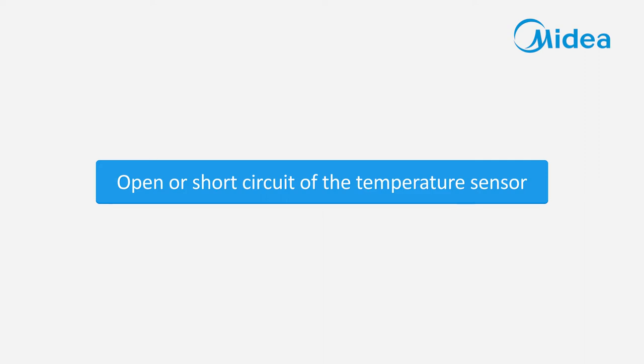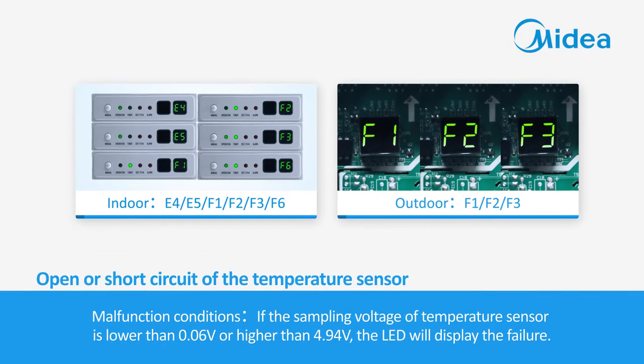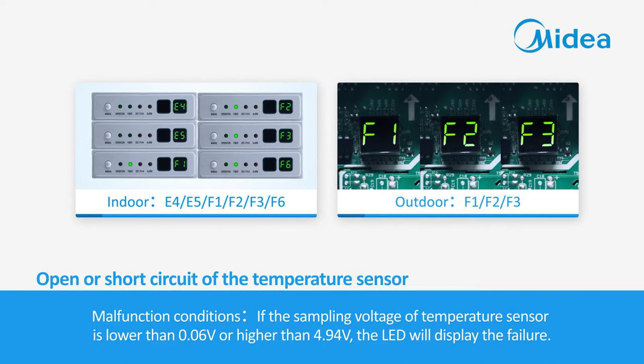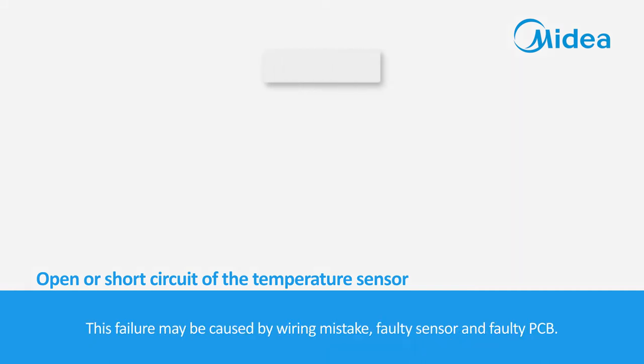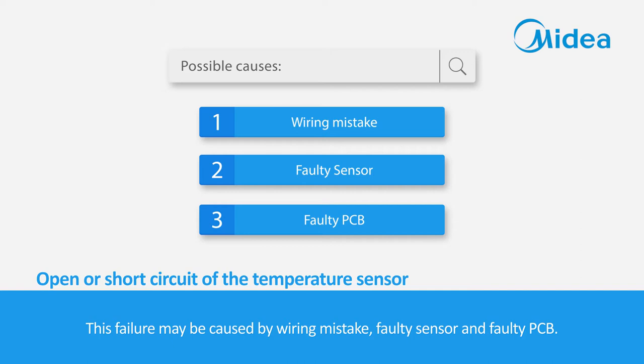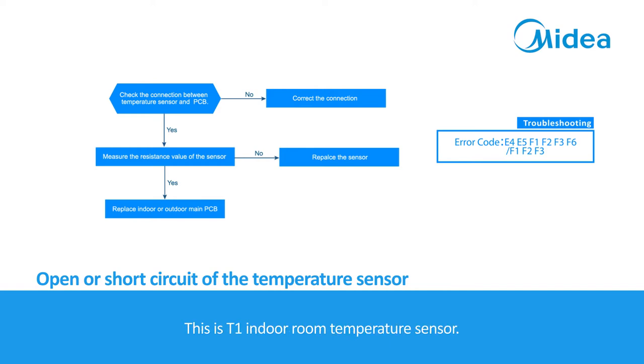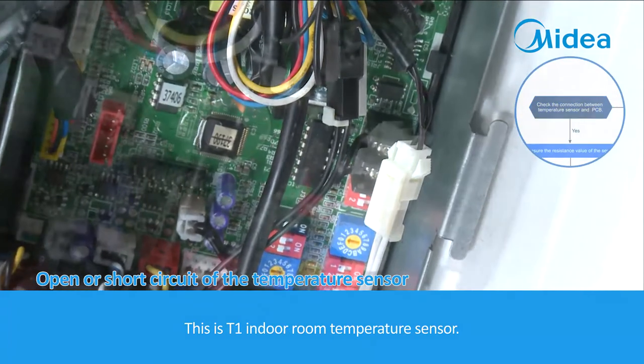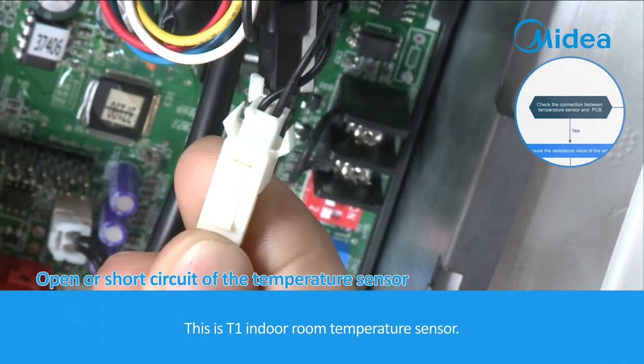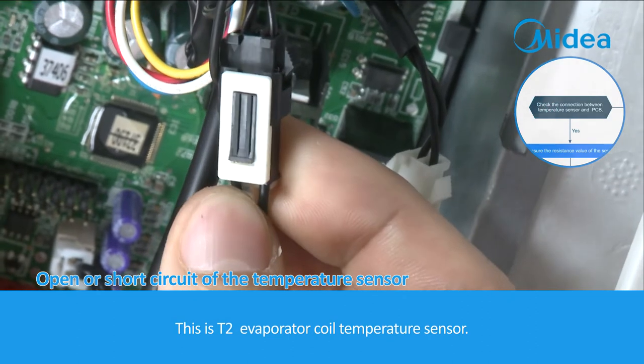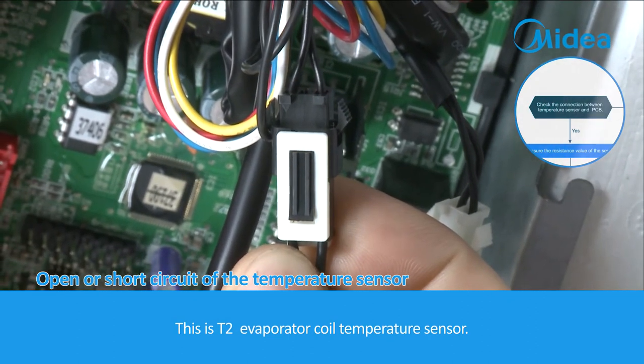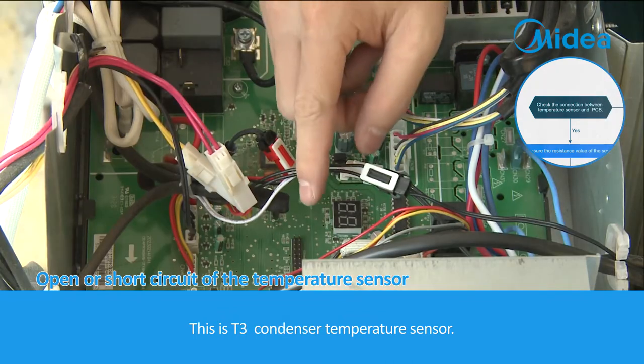Open or short circuits of the temperature sensor. Malfunction conditions: if the sampling voltage of the temperature sensor is lower than 0.06 volts or higher than 4.94 volts, the LED will display the failure. The failure may be caused by wiring mistake, faulty sensor, or faulty PCB. This is T1, the indoor room temperature sensor. This is T2, the evaporator coil temperature sensor.